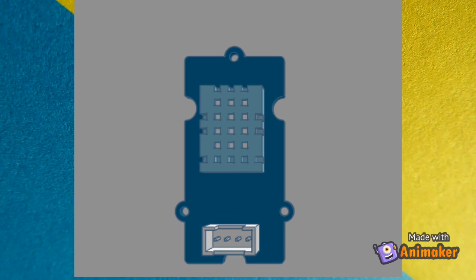The temperature and humidity sensors were mounted onto the wall at each side, on top of the air vents. They sense the air temperature coming in and going out. The temperature going out through the return vent must be 14 to 20 degrees cooler than the air coming in through the supply vent. By maintaining this temperature difference, air convection is introduced, ensuring constant systematic air circulation within the laboratory. The warm air comes in, while the cool air goes out.